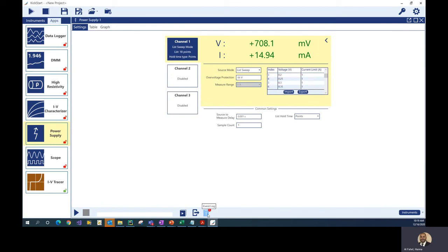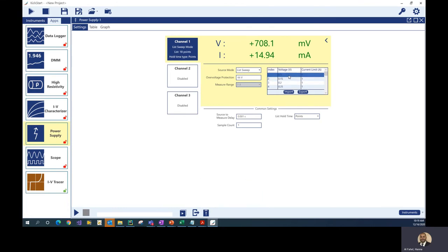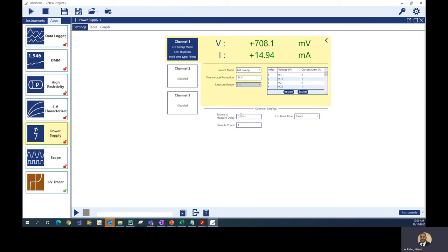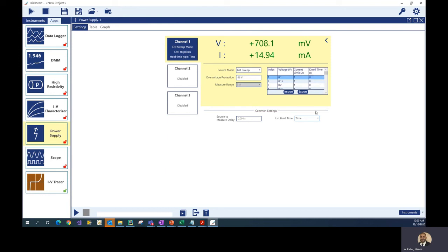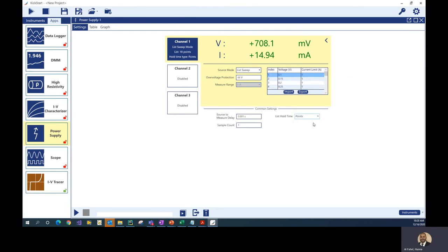The import is complete — you get a message in the event log confirming the CSV file has been imported. In this list I'm sweeping voltage from 0.1 volt to 0.95 volt with a current limit of 1 amp, in order to look at the output characteristics of a diode. I'll leave the common settings at default — such as source-to-measure delay and list hold time — though you could add a dwell time at each point if needed. We're ready to run, so let's hit Run.